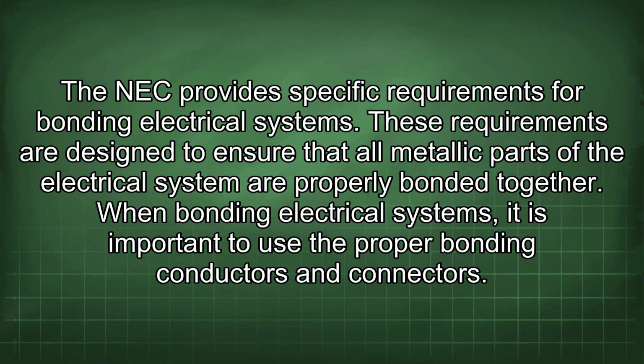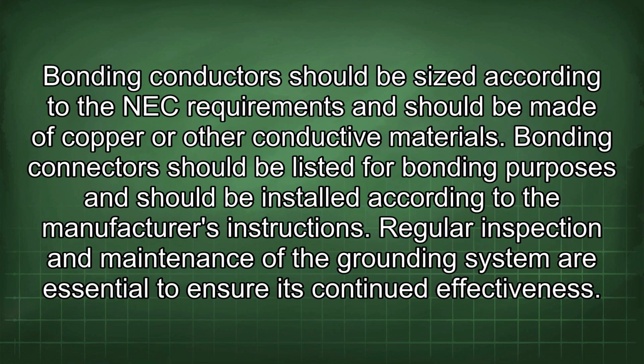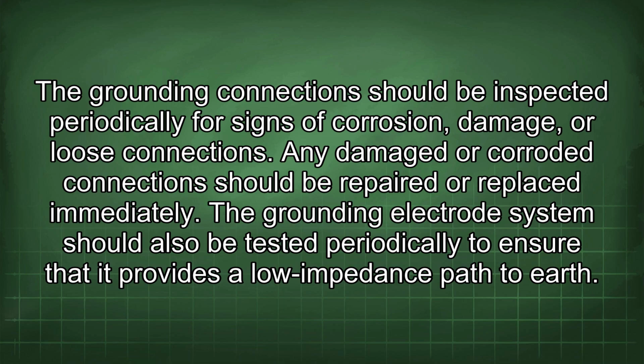When bonding electrical systems, it is important to use the proper bonding conductors and connectors. Bonding conductors should be sized according to the NEC requirements and should be made of copper or other conductive materials. Bonding connectors should be listed for bonding purposes and should be installed according to the manufacturer's instructions. Regular inspection and maintenance of the grounding system are essential to ensure its continued effectiveness. The grounding connection should be inspected periodically for signs of corrosion, damage, or loose connections. Any damaged or corroded connection should be repaired or replaced immediately. The grounding electrode system should also be tested periodically to ensure that it provides a low impedance path to earth.